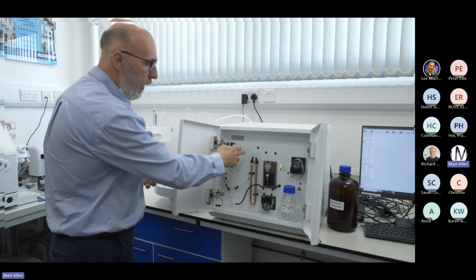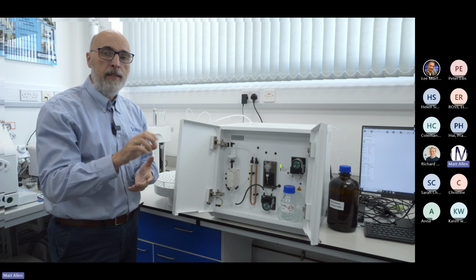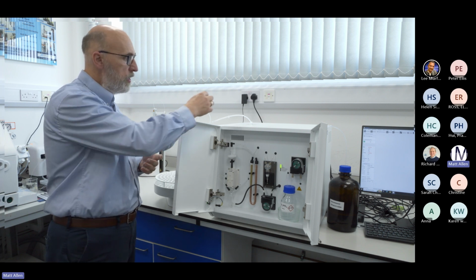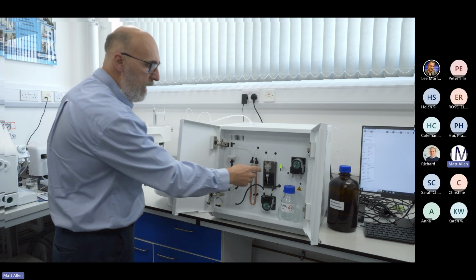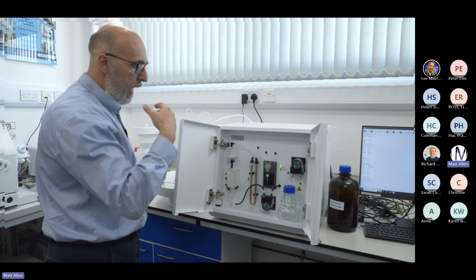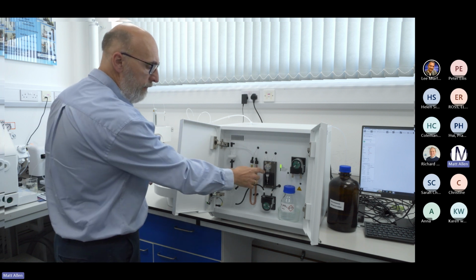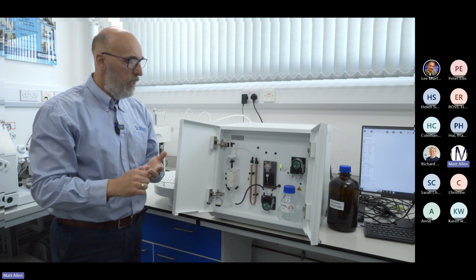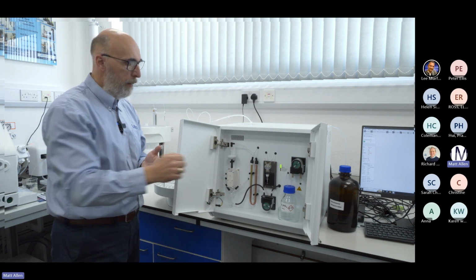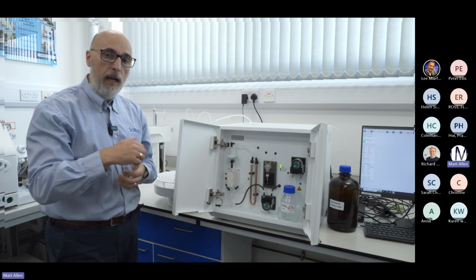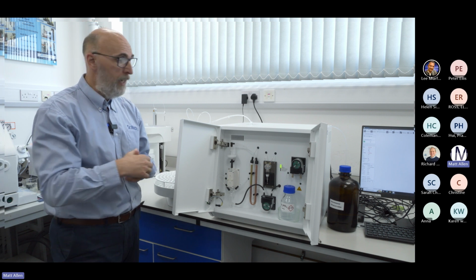And you might just think that's a standard syringe pump. But what's really great is behind here, where unfortunately you can't see, there's a sample loop. What it means is the sample, when we're bringing it in here, only ever gets introduced to the loop itself. It never comes into this syringe pump. Now, there are other designs of systems on the market where the sample does potentially come into the syringe pump. If you've got any particulates or anything like that in your sample, they can damage the transfer line, they can damage the seal, and basically over time you don't get as good repeatability, and also you get carryover with these particulates being left behind in the syringe pump and being carried over to one or the other.